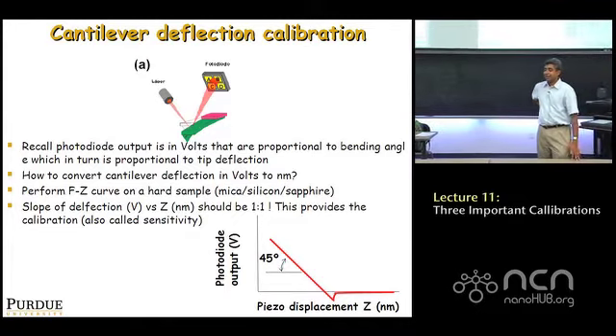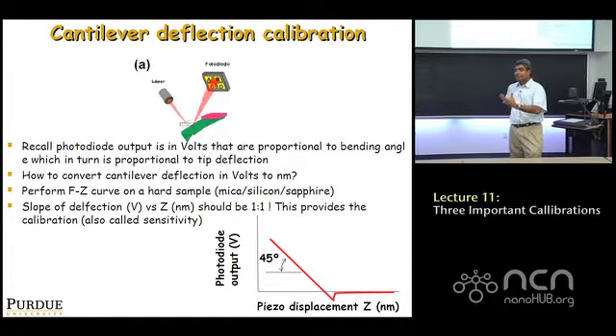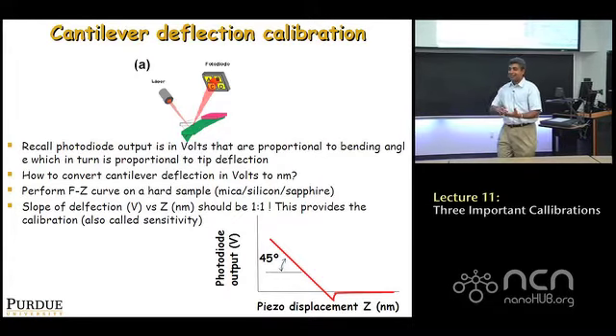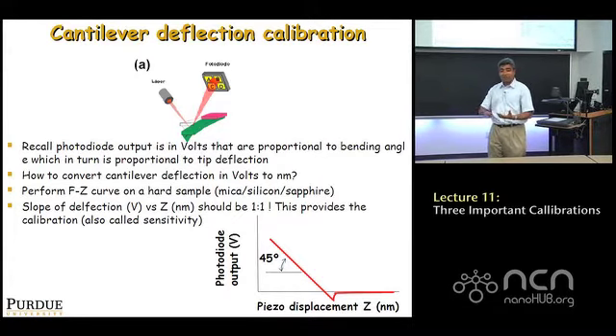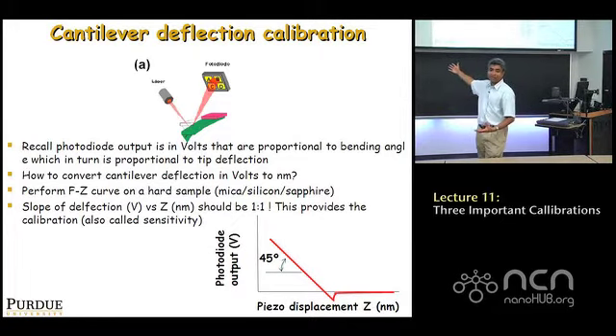This depends. If you're trying to measure the stiffness of a very stiff object, then this calibration needs to be done on an even stiffer object, right? So let's say your job is to figure out the elastic modulus of mica using AFM. That's difficult because to measure the stiffness, you have to do this calibration on something else. This calibration assumes that the sample is infinitely rigid, right? So if you do this calibration on mica and then try to measure stiffness on mica, what elastic modulus are you going to get? You're going to get infinity, because you've done the calibration assuming mica is infinitely stiff.